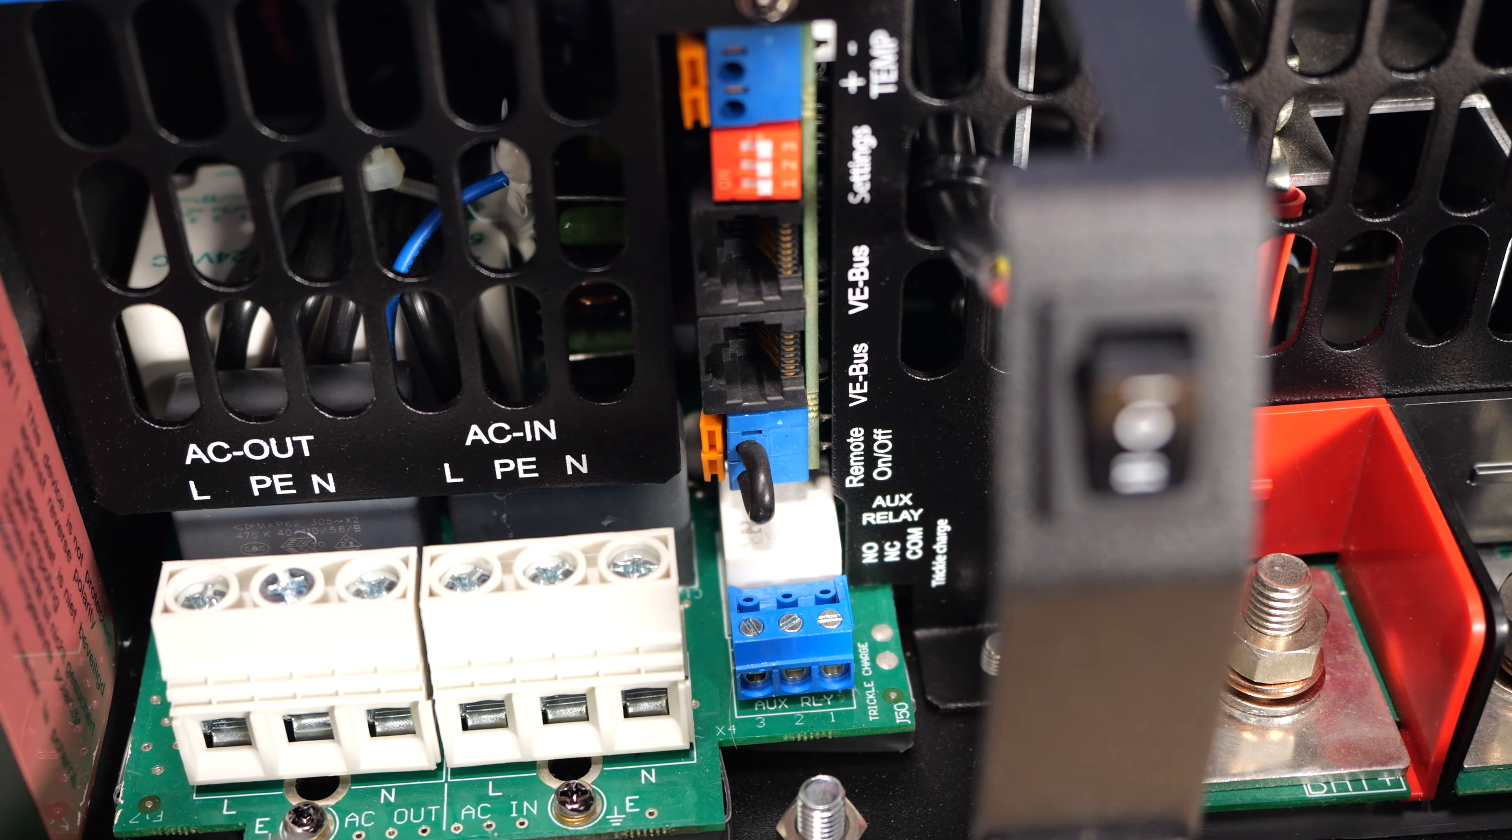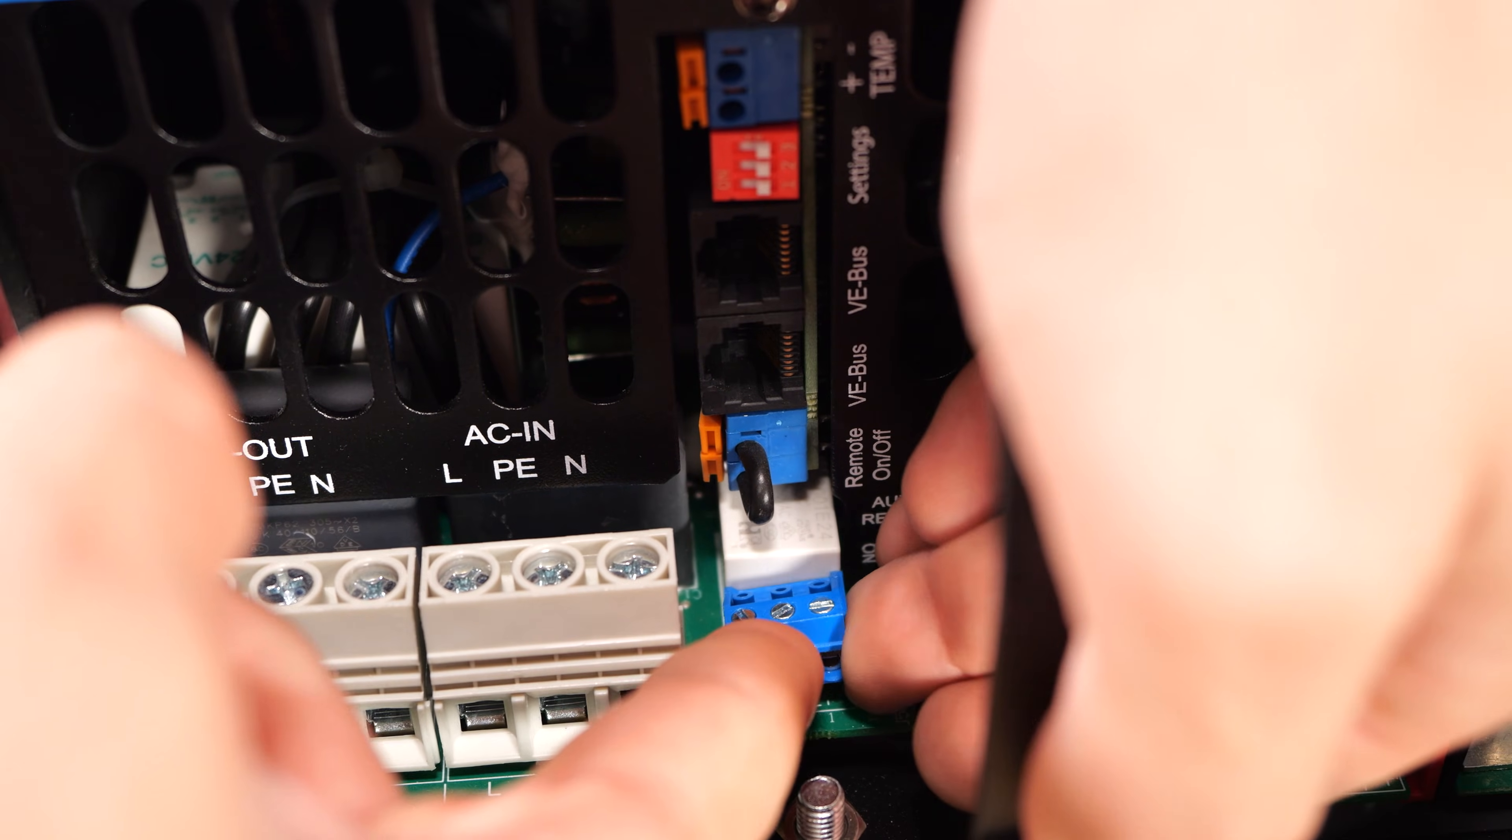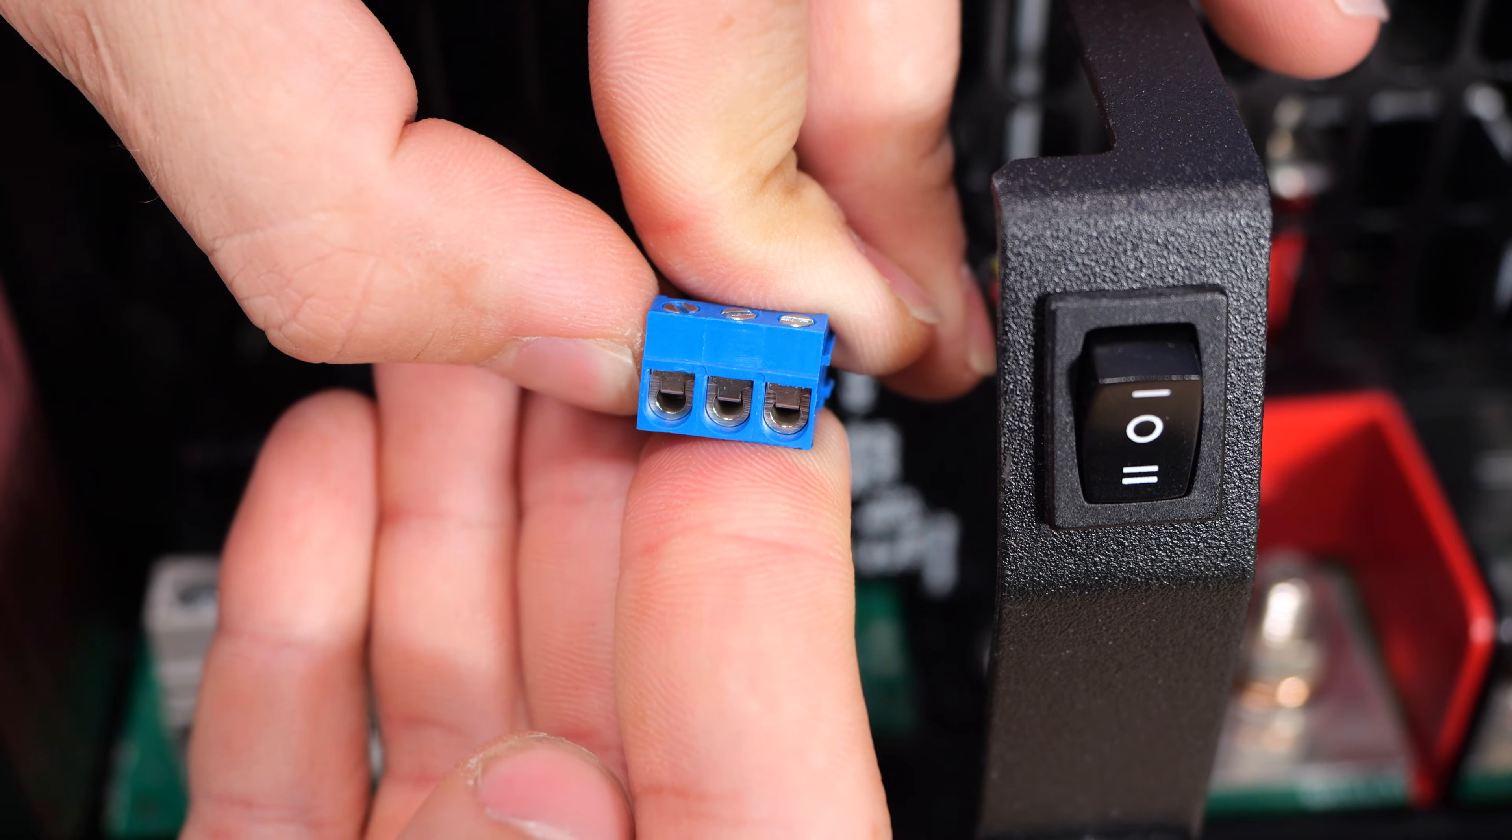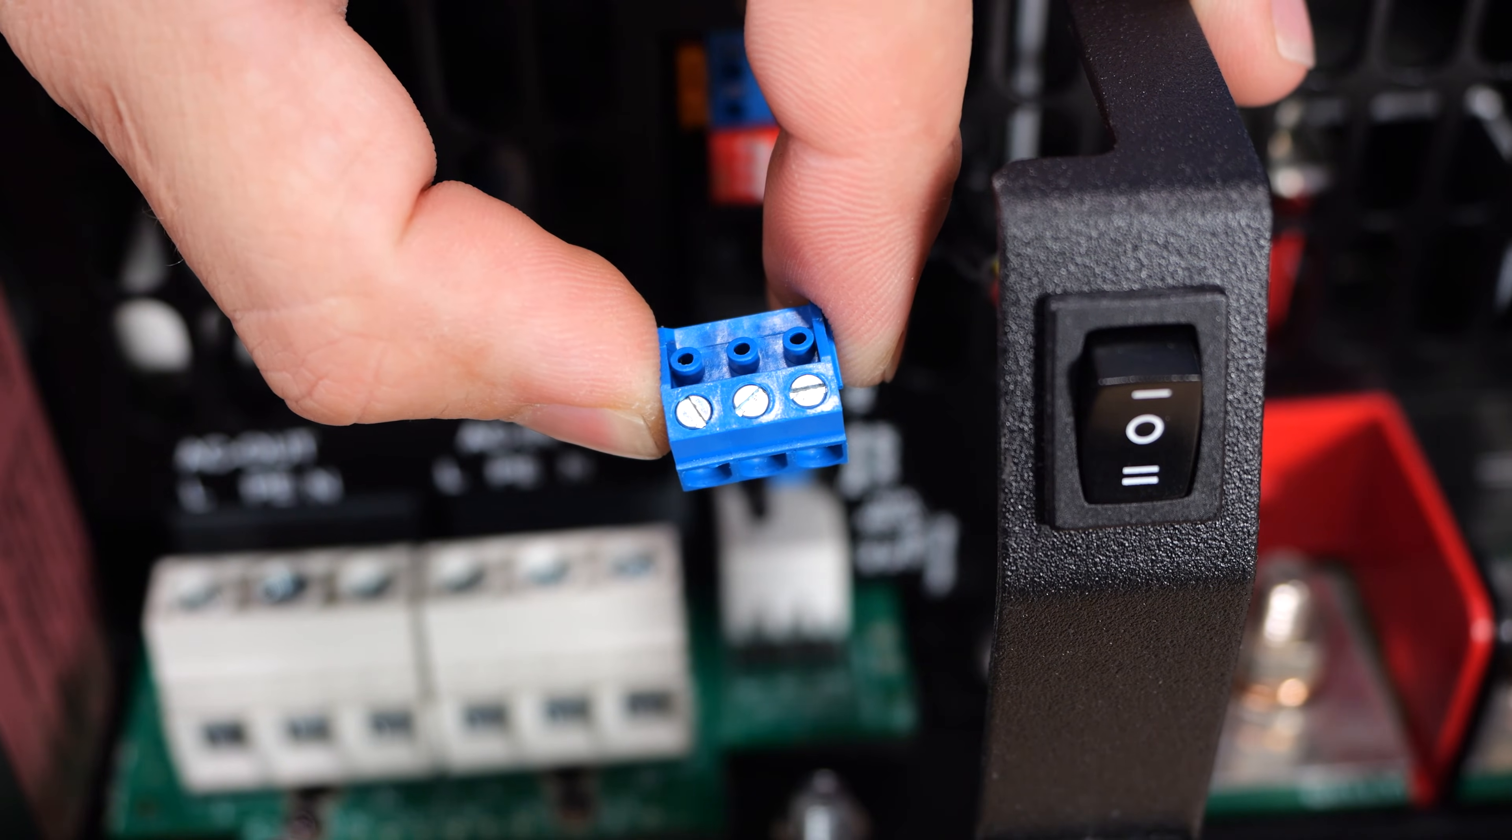We have some auxiliary connections in here. There is this blue dry contact terminal block. This can simply be lifted up here and removed to make your electrical connections onto. And then once you've made your connections, it just pushes right back onto the pins. This can fit up to 14-gauge wire, although 14-gauge is a little bit of a tight fit. 16-gauge would be more optimal.